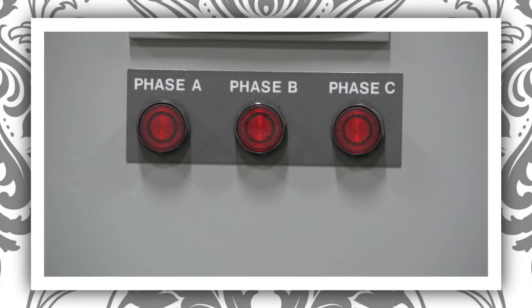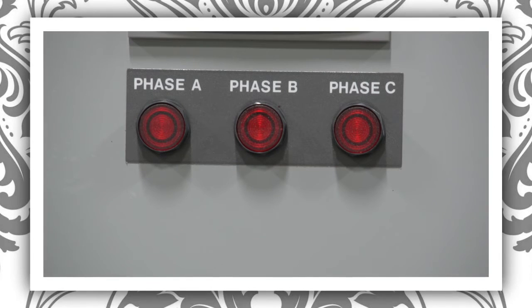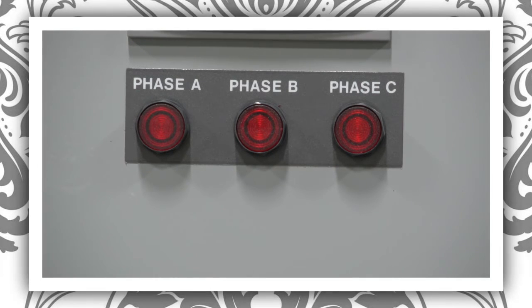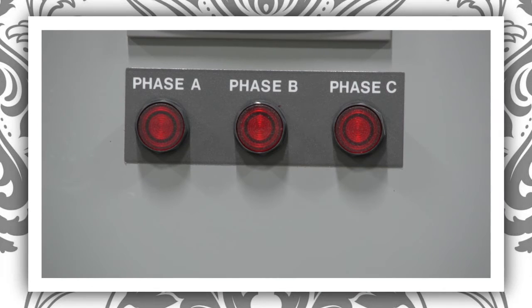So using high-resistance grounding, you can use the current device and measure the current throughout conduits throughout the system and try to figure out where exactly the ground fault is.